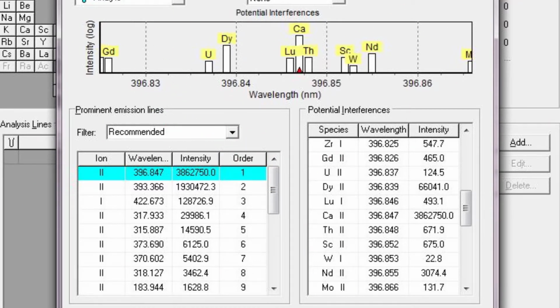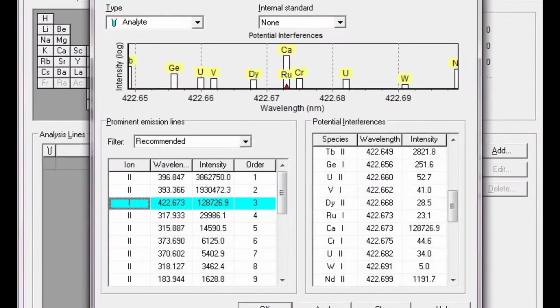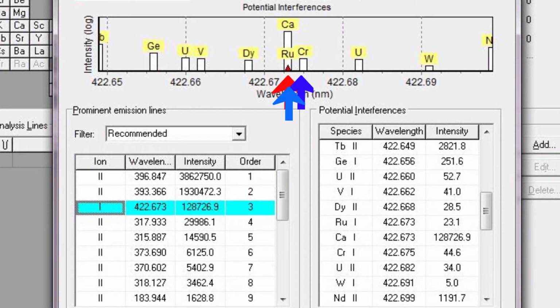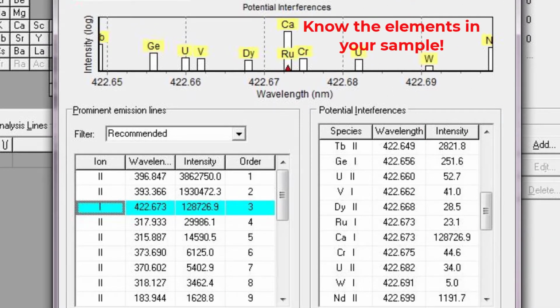Unfortunately, it's very common for a wavelength of one element to overlap with the wavelength of another. As you see here, thorium and lutetium are extremely close to the signal for calcium. So if either of these elements are in the same sample, this would be a poor choice for your analysis. If you left-click on a different wavelength, you'll see that the elements that can potentially interfere will be different. So it's important to have a good idea of which elements are in your sample so that you do not get a falsely high concentration in your final analysis.